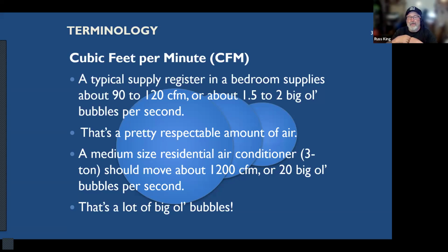They typically don't. The air handler that's attached to this 5-ton air conditioner needs to and wants to move 2,000 of these bubbles through the duct system. But if you don't size the ducts correctly, there's not enough room. There's too much resistance. It's trying to push air through a pinched-off straw. And then what happens is the air backs up.